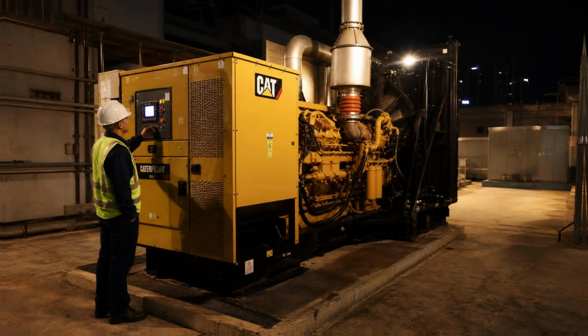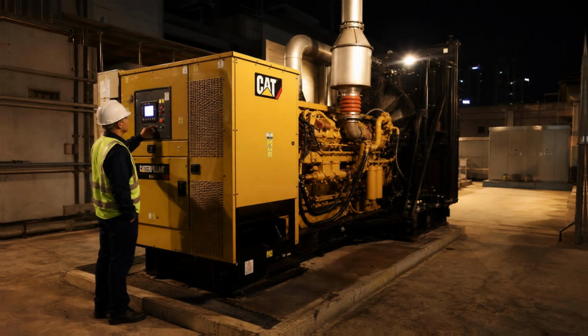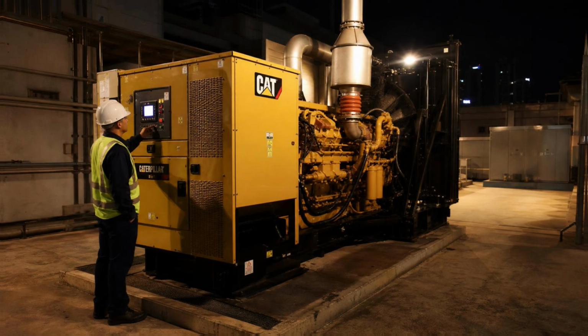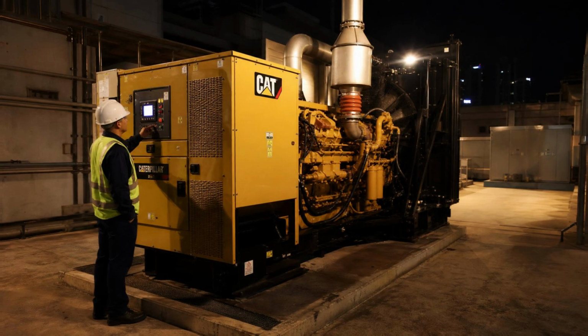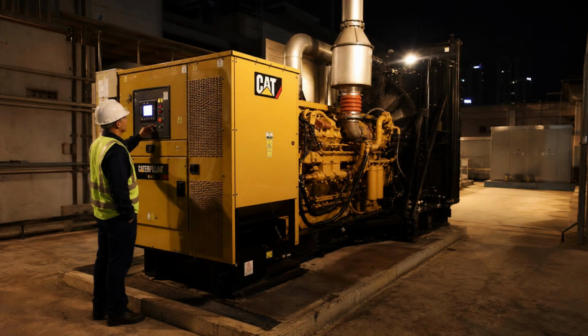In most commercial and institutional emergency power installations, the fuel that sustains the generator through an outage is diesel. Diesel fuel is the standard for this application for reasons that are practical and well established. It is stable enough to store for extended periods. It is energy-dense enough to allow meaningful runtime from tanks of manageable size, and the diesel engine is a proven technology with a long and reliable history in standby power applications. When you imagine a generator room, the smell you might associate with it, that faint particular scent of petroleum that hangs in the air even when the engine is not running, is mostly the smell of diesel, the fuel in the lines, the residue on the fittings, the trace of the last exercise run that settled into the room and never quite left. The fuel system begins at the storage tank.